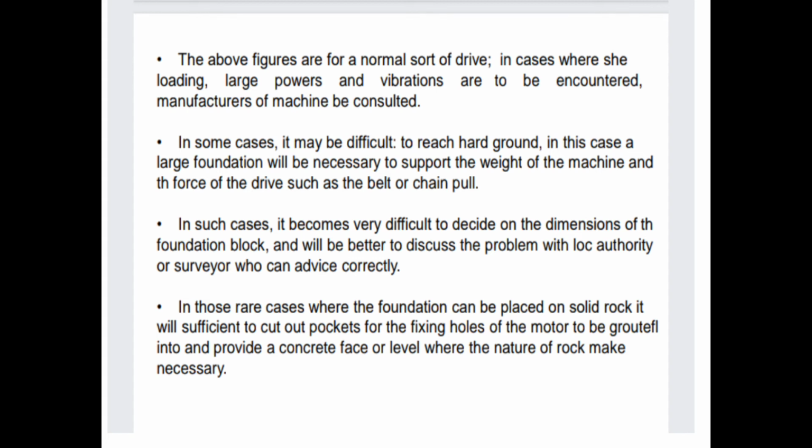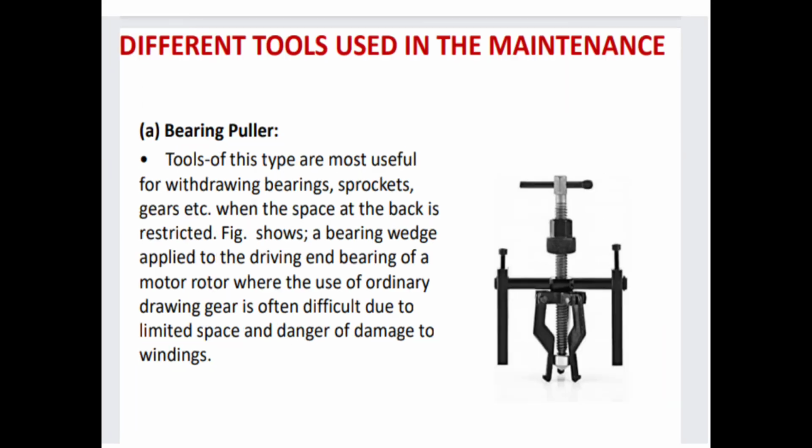In those rare cases where the foundation can be placed on solid rock, it will be sufficient to cut out pockets for the fixing holes of the motor to be grouted into, and to provide a concrete floor or levels where the nature of the rock makes it necessary. So this is about the requirements for the rotating machine foundation.